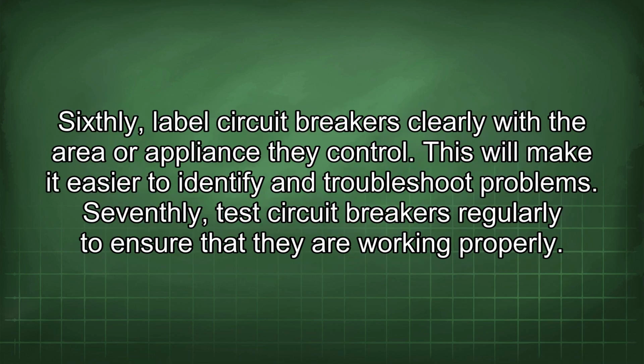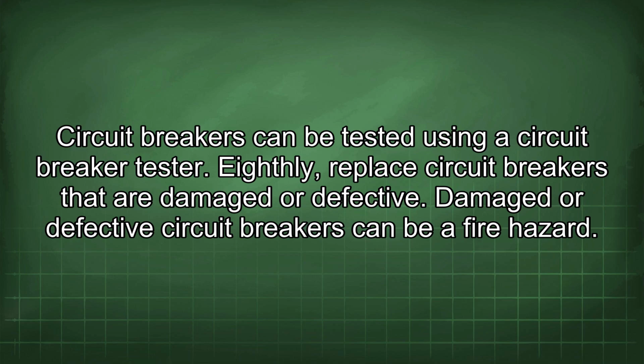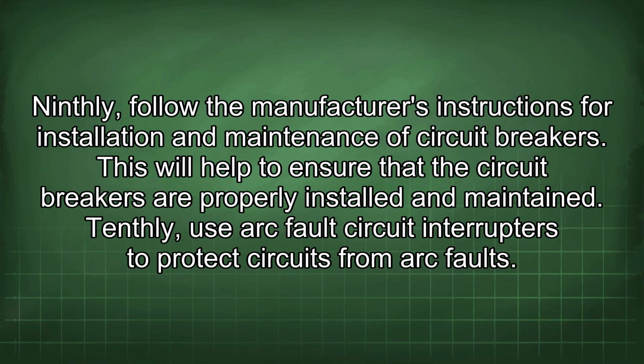Sixthly, label circuit breakers clearly with the area or appliance they control. This will make it easier to identify and troubleshoot problems. Seventhly, test circuit breakers regularly to ensure that they are working properly. Circuit breakers can be tested using a circuit breaker tester. Eighthly, replace circuit breakers that are damaged or defective. Damaged or defective circuit breakers can be a fire hazard. Ninthly, follow the manufacturer's instructions for installation and maintenance of circuit breakers. This will help to ensure that the circuit breakers are properly installed and maintained.